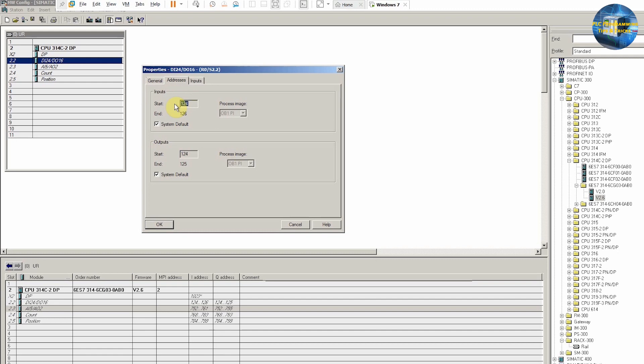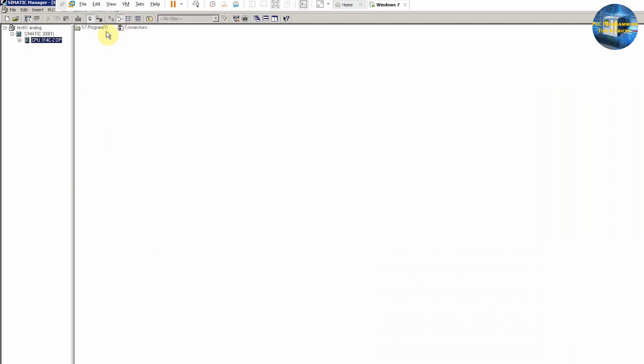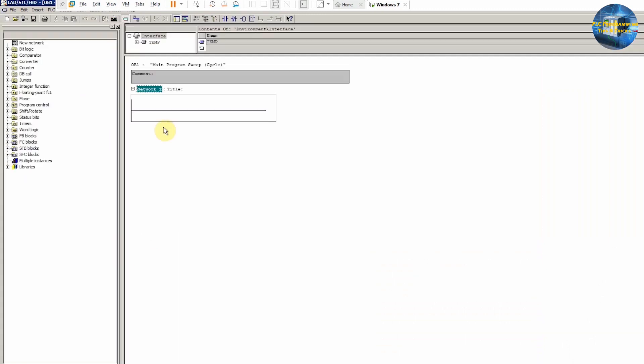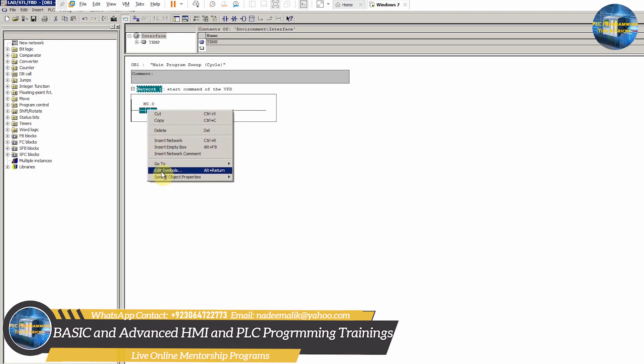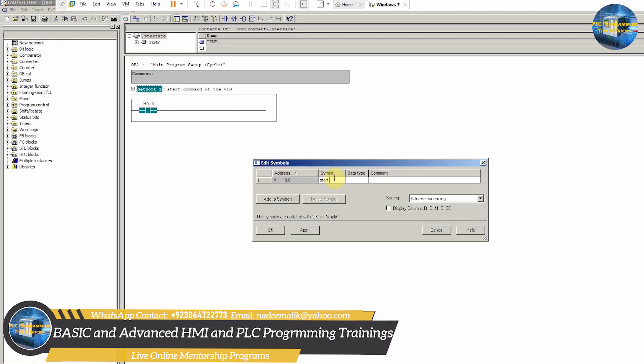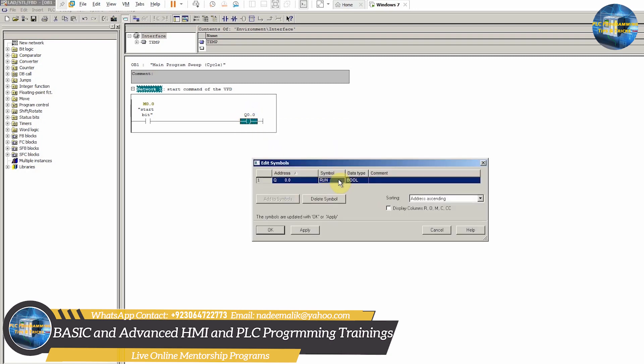Next we will open the digital I/O settings. We can change the addresses of the digital I/Os in this menu — we will change the start address to zero so these I/O addresses will start from zero. Next we will save and compile this file, and our hardware configuration is finished. We will then open the programming blocks and open the OB1 block. In network 1 we will make logic to start the VFD using the M0.0 start bit to turn on the Q0.0 output of the PLC.